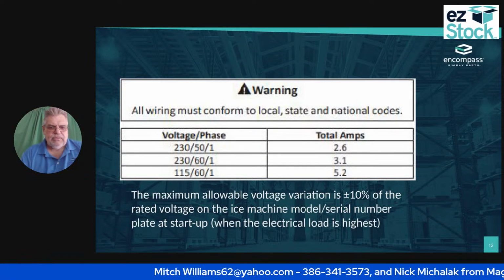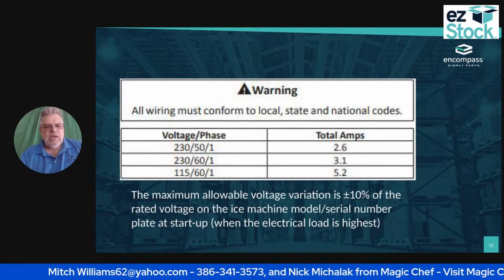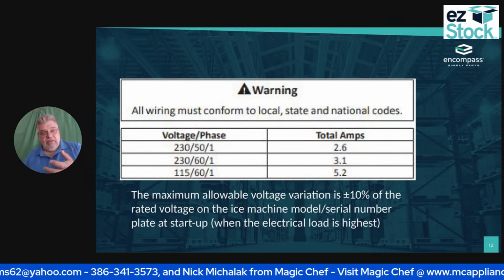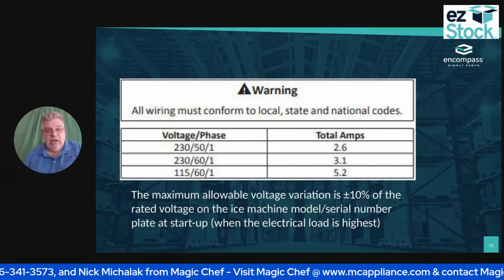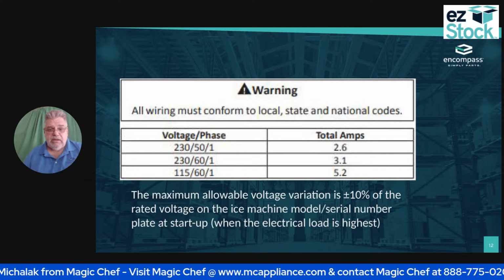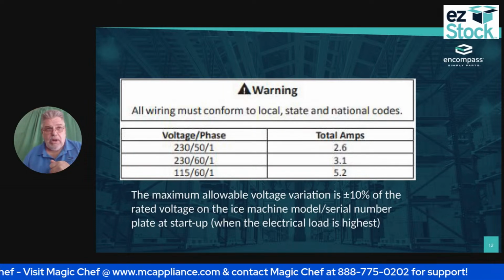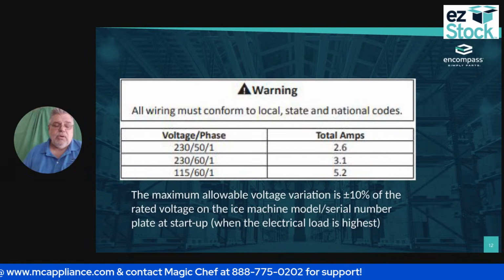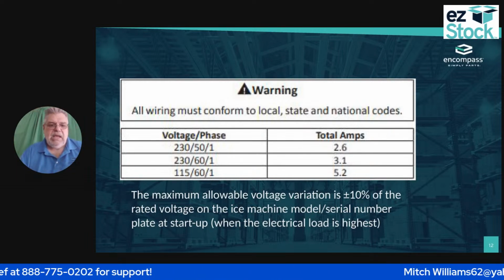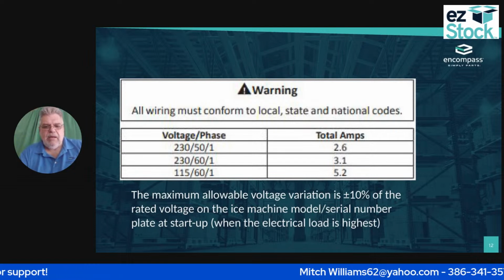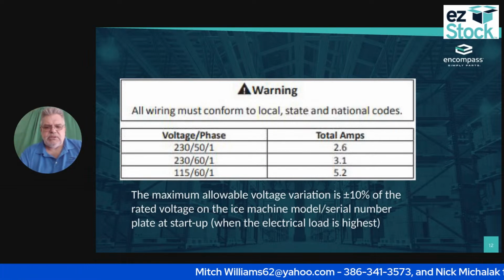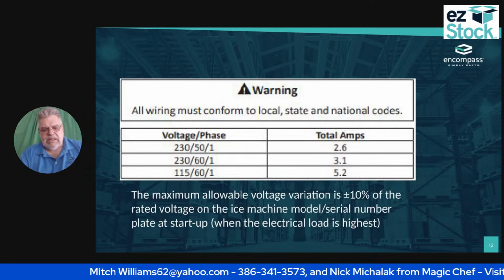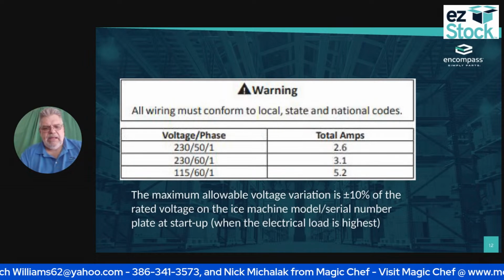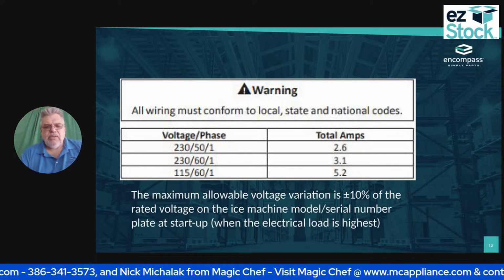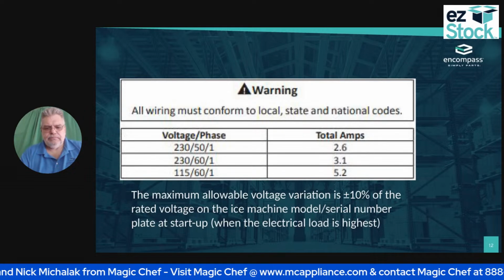Not quite, but close. Okay. So that just goes to show you, it's just like a regular air conditioner. If I have a 110 volt air conditioner, I'm going to pull a whole lot more amps than if I have a 230 volt air conditioner. I'm not going to pull that many amps. The maximum allowable voltage is plus or minus 10% of the rated voltage on the ice machine, and that is shown on the model serial plate.